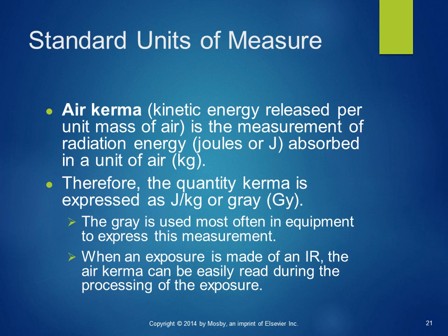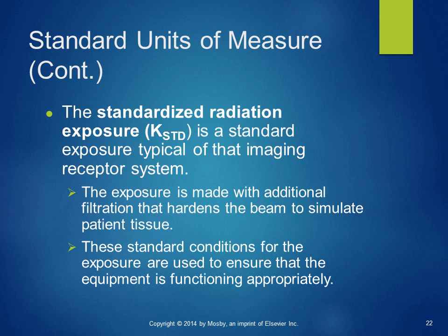When an exposure is made of an IR, the air kerma can be easily read during the processing of the exposure. The standardized radiation exposure, KSTD, is a standard exposure typical of that of an imaging receptor system. The exposure is made with additional filtration that hardens the beam to simulate patient tissue. These standard conditions for the exposure are used to ensure that the equipment is functioning properly.